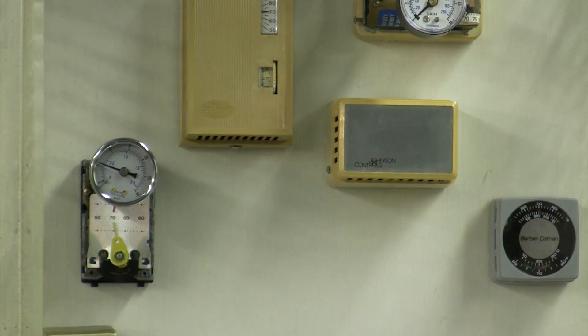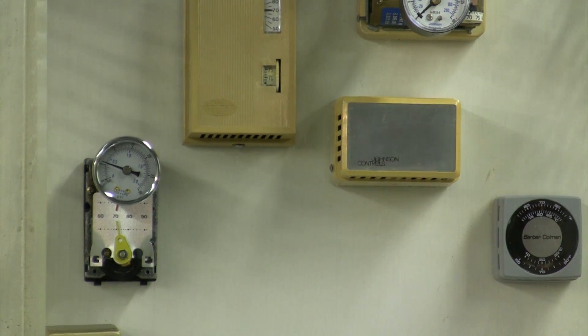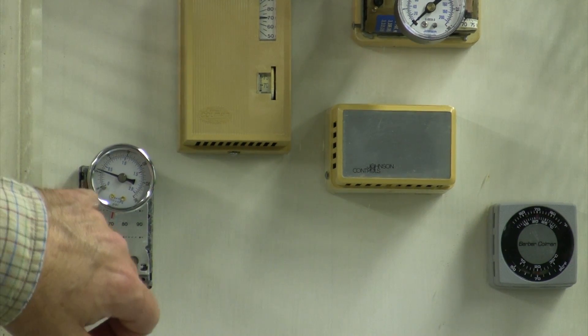Alright, now in each case I'm gonna look for about a ten and a half pound branch pressure. Let's start with the Honeywell first. I've got my branch gauge right here, and it is reading just a little over five pounds.